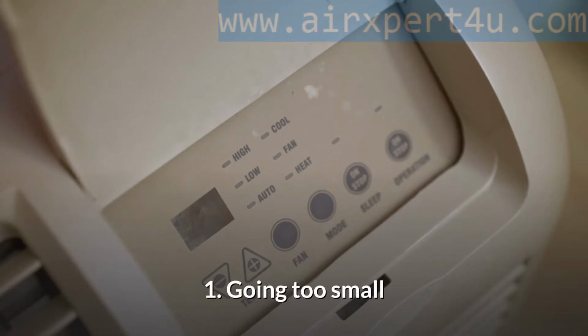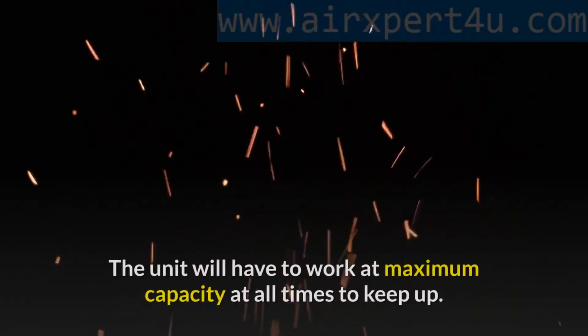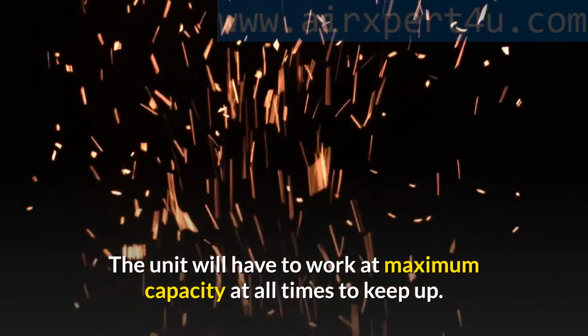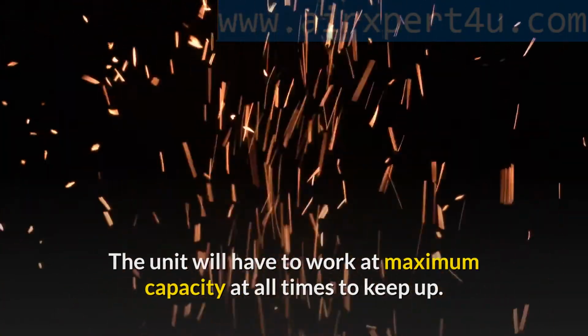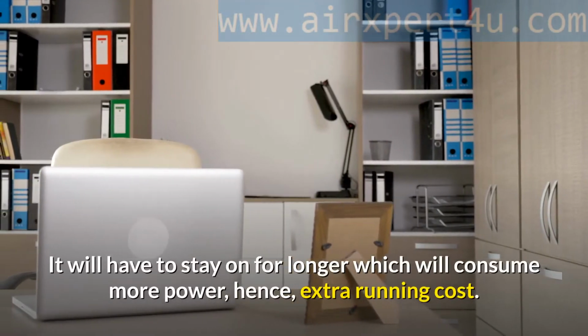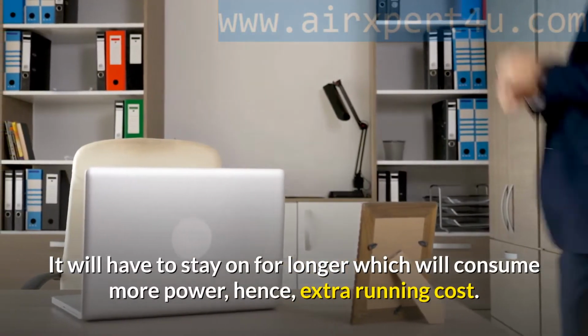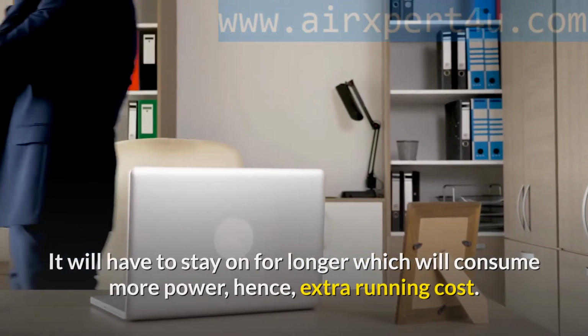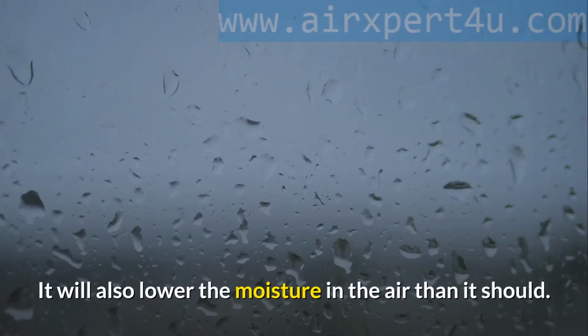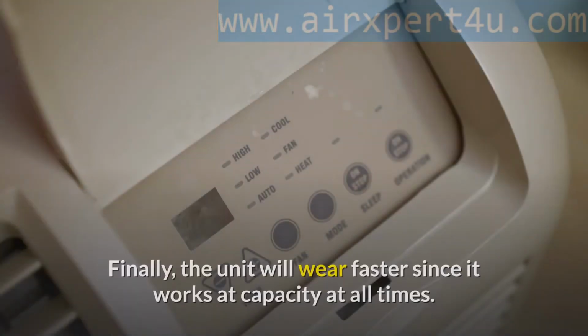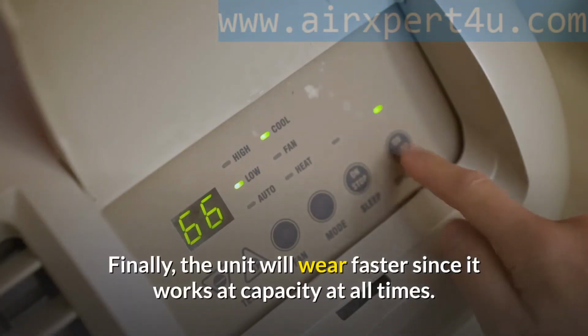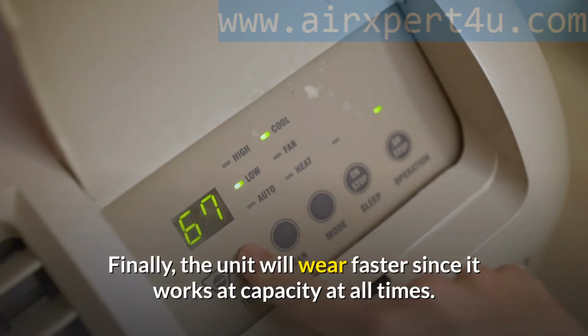1. Going too small. The unit will have to work at maximum capacity at all times to keep up. It will have to stay on for longer, which will consume more power, hence, extra running cost. It will also leave more moisture in the air than it should. Finally, the unit will wear faster since it works at capacity at all times.